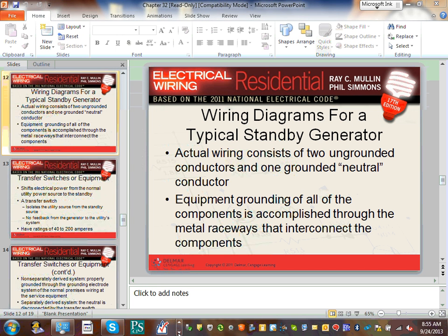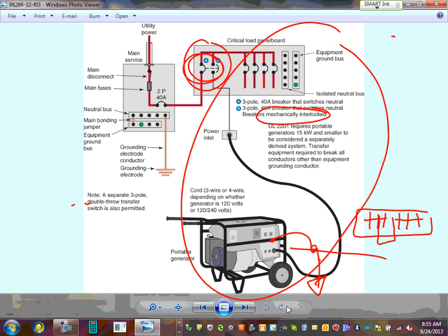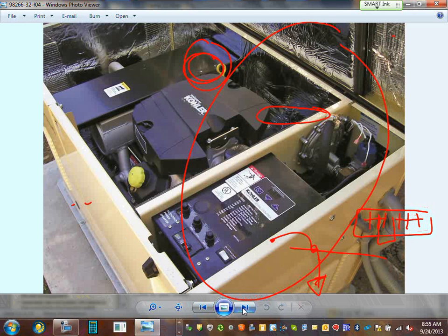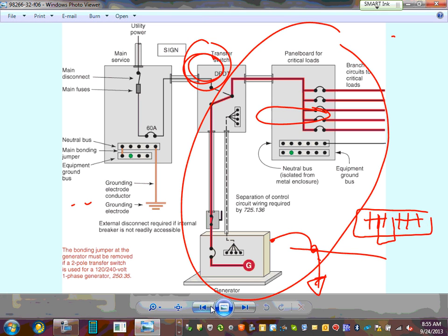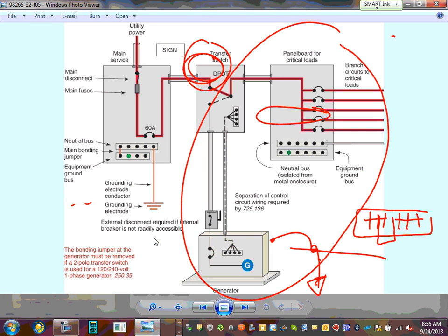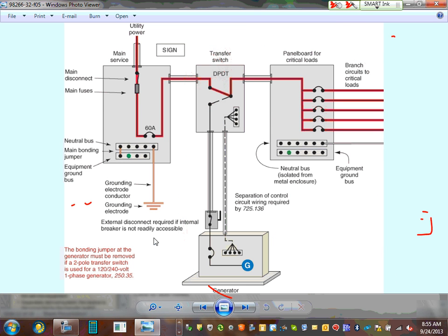Let me go to the wiring diagram of that one, because I thought it's interesting. Okay, here's your next step. Let's go back here. There you go. This is the top of the line for dwellings, if you guys want to do it. Look at this. Now I have a permanently installed generator. I do have an auto transfer switch. Can you guys see an auto transfer switch? Permanently installed generator, auto transfer switch, has an overcurrent protection device in there. Sometimes you might need a disconnect if you don't have access to the overcurrent protection device.